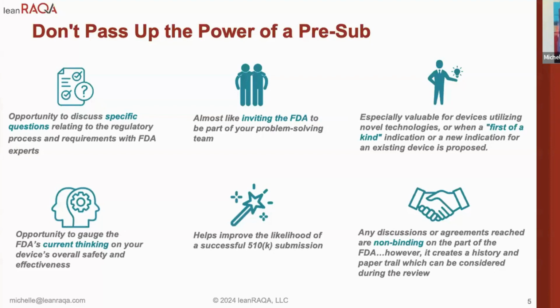They're really valuable if you have anything new or novel about your technology, especially if you are trying to get something that's similar but different from your possible predicate through the FDA via 510(k).